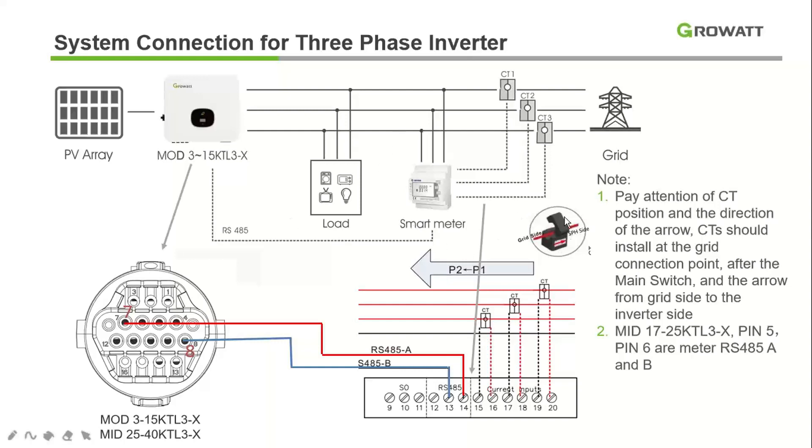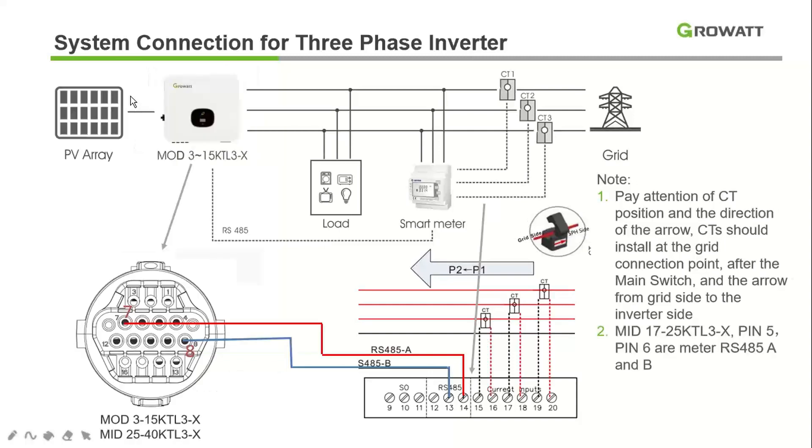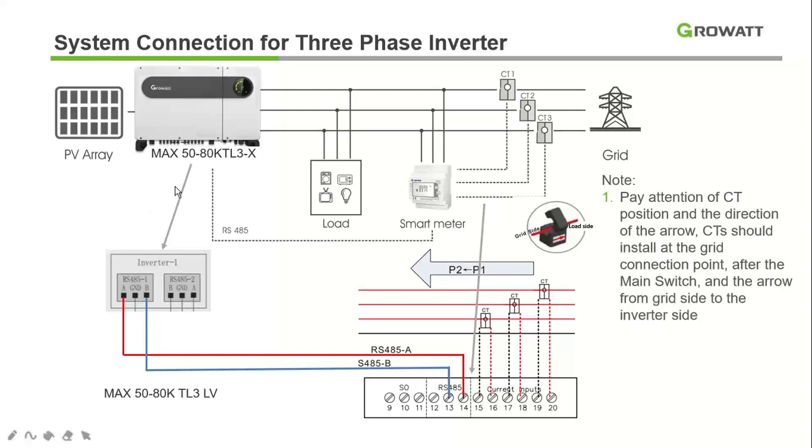The direction of the CT plays a very important role for efficient working of zero export functionality — always verify CT orientation. For the MAX series (50–80 kW), the RS-485 connection is different: it has a separate RS-485 pin connector at the termination points. Simply connect point A to A and point B to B of the meter. All other connections remain the same.